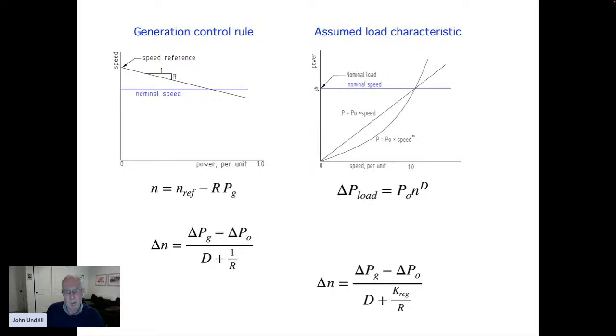We've assumed for most of the life of the industry, since perhaps 1900 through perhaps 2000, that the load on the power system would not be constant, but would increase as the speed increases. Well, if you think of the load being light bulbs, this is not true. The power would be constant as speed changes. But if you think of the load as conveyor belts and quarries and factories around the power system, as the speed increases, the load increases. And it could be linear if the load is conveyor belts and things like that. It could be a power law, a square law, or a cube law if the load is pumps or fans.